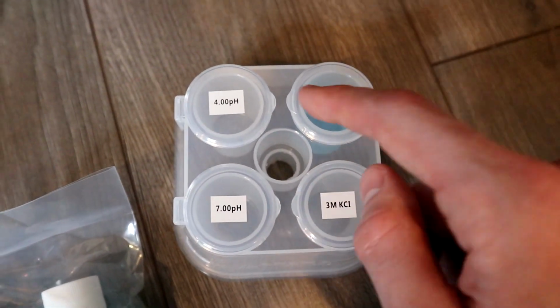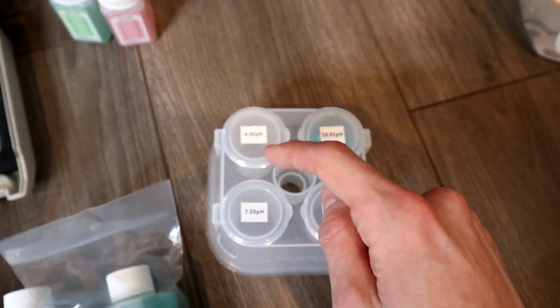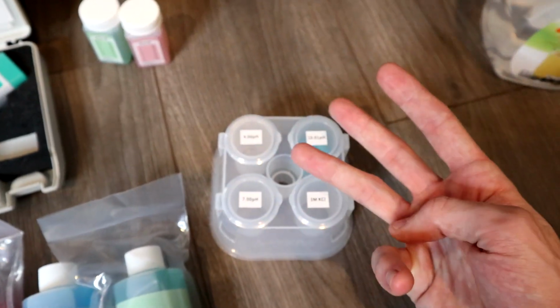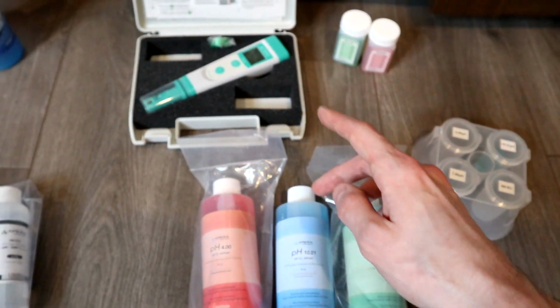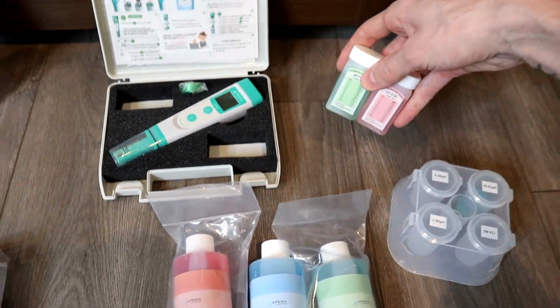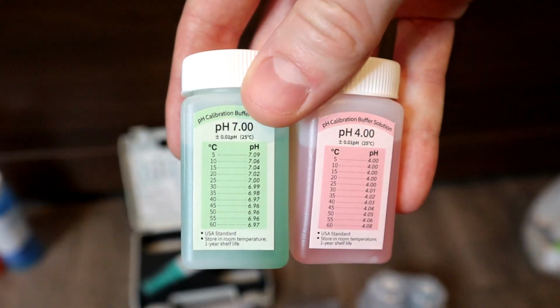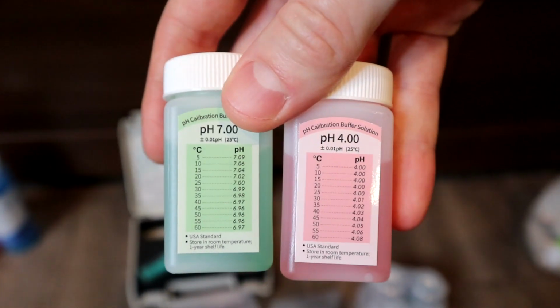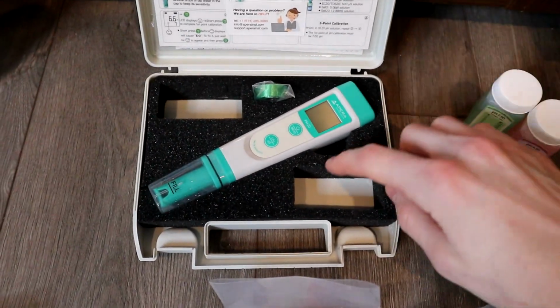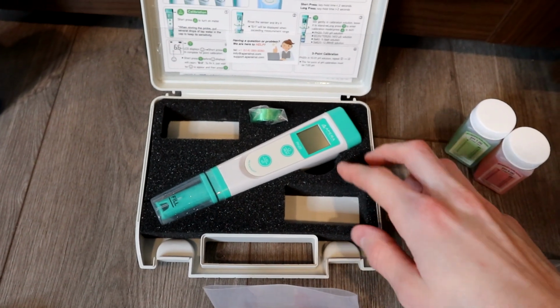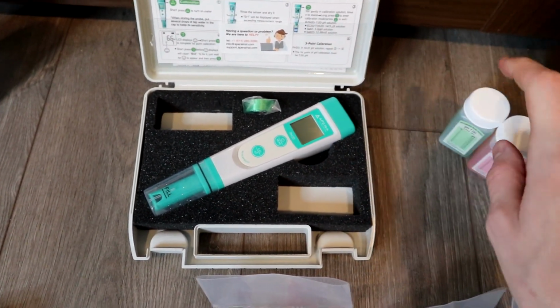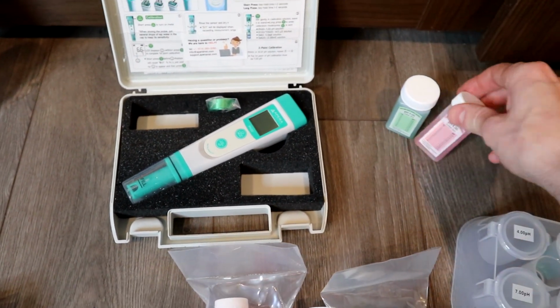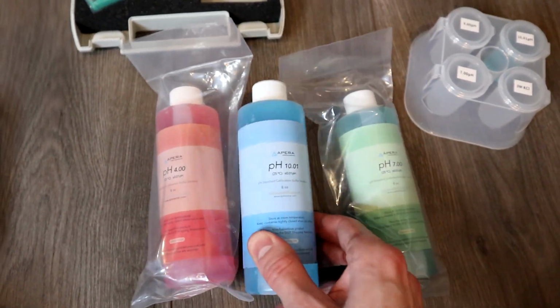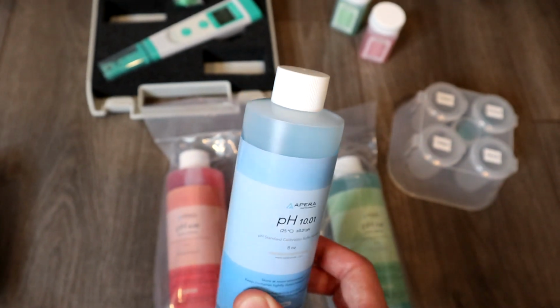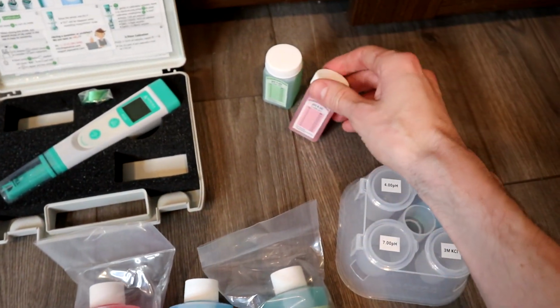And then the remaining 3 are each for 1 point of calibration, for a total of 3-point calibration that this meter allows. It already comes with pH of 7 and pH of 4 solutions. That's what those spaces there are for. So right out of just the little box, you can 2-point calibrate it, just dipping them right into these jars. But of course, this kit comes with the 3rd fluid, so you can see that's the only one I've opened, because it doesn't have a little version of it.